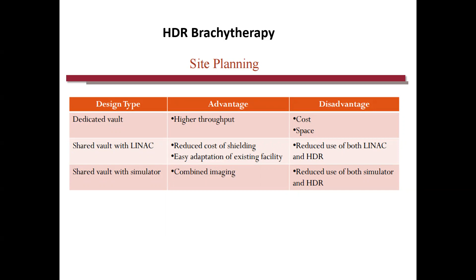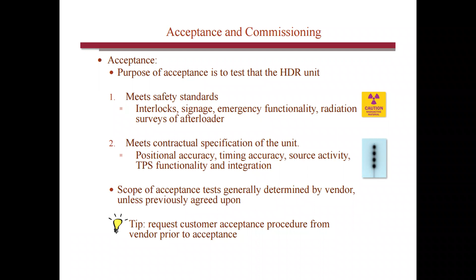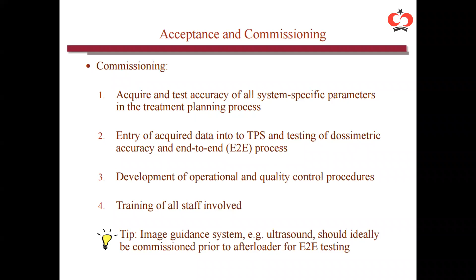Acceptance testing and commissioning of the HDR unit is quite standard. We need to check the safety standards, whether we are meeting the contractual specifications of the unit, and certainly other parameters which were agreed upon. The commissioning is the end-to-end test and all the required tests, training of the staff, and development of the quality assurance procedures. Do we need to know about the QA, QC and acceptance commissioning of the HDR? So these are some of the references.